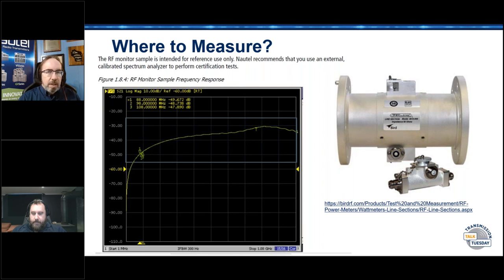William's asking if he should be pulling the couplers out every few years to send them in for calibration. The short answer is, ideally, if you're planning on using them for any critical measurement, like your harmonics and spectral compliance, then probably yeah—short of having two of them, having one calibrated and sitting on the shelf, and just swapping them every year or two.